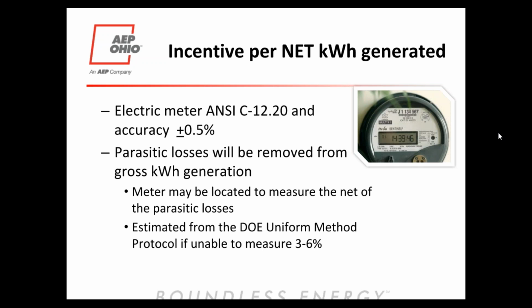Parasitic losses will be removed from the gross kWh generated, and these may be calculated by the customer based on placement of other meters. However, if the losses cannot be calculated, we'll use the DOE estimated losses, which range from 3 to 6%, depending on the technology used in the CHP system. For example, a gas turbine would be at the 6% range, while something smaller like a microturbine would be closer to 3%.